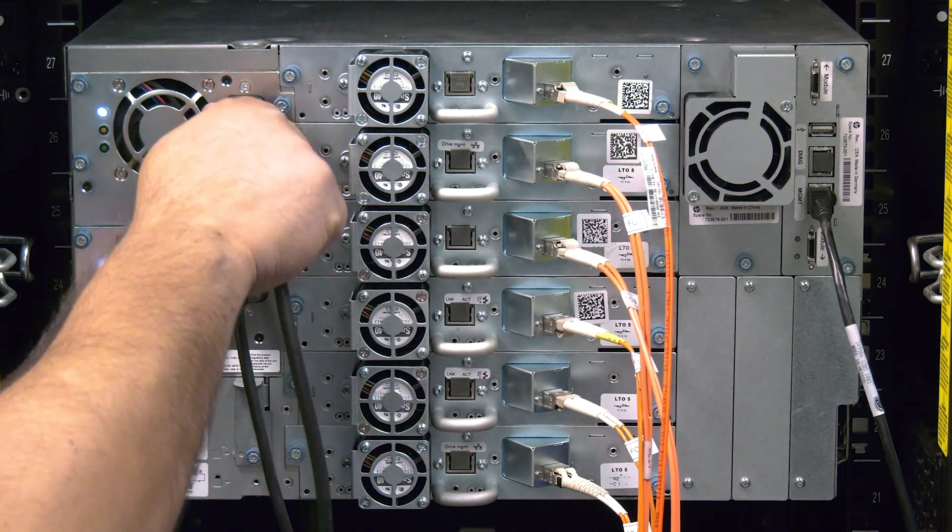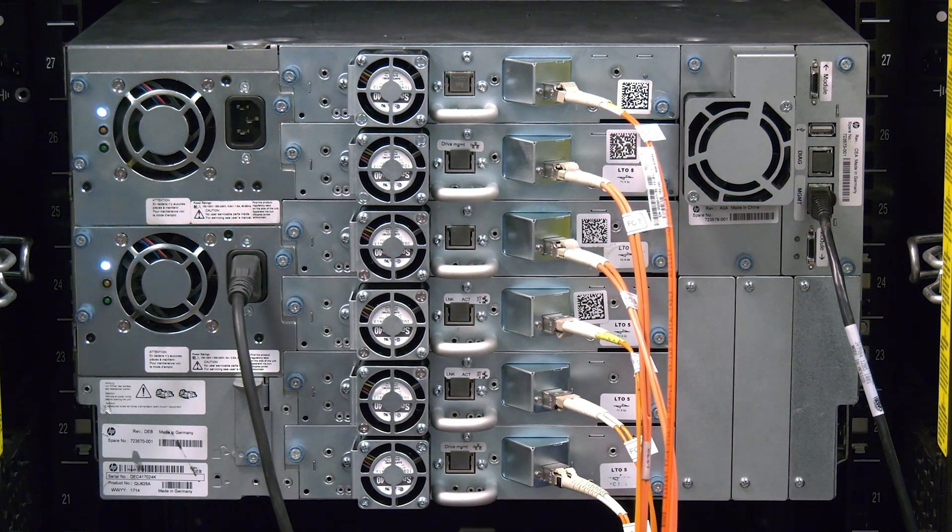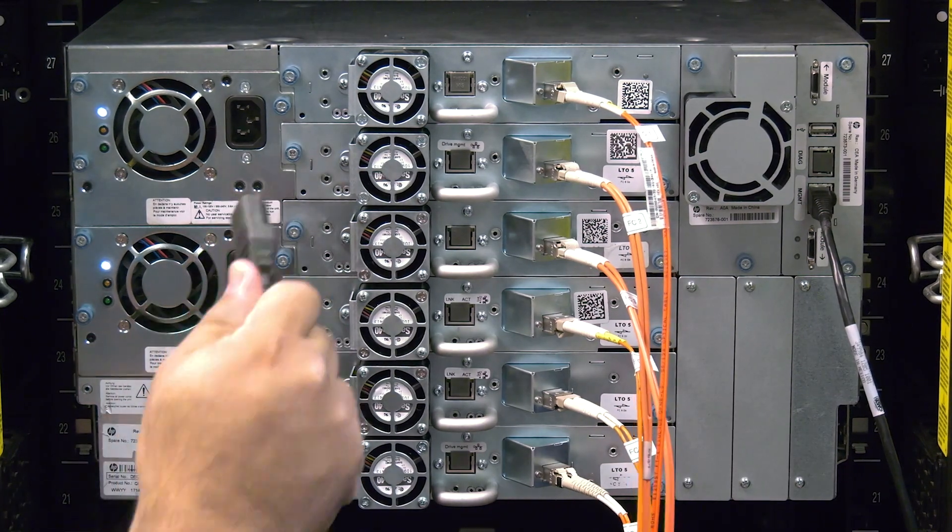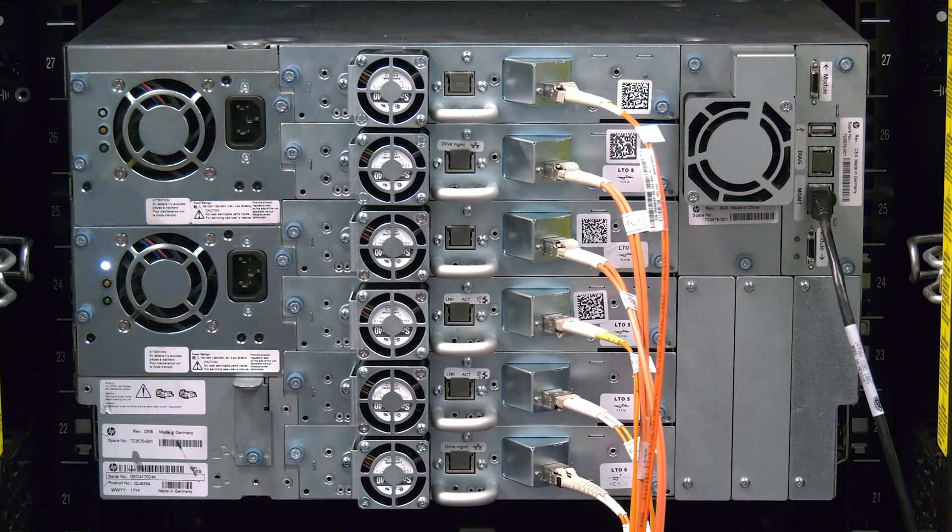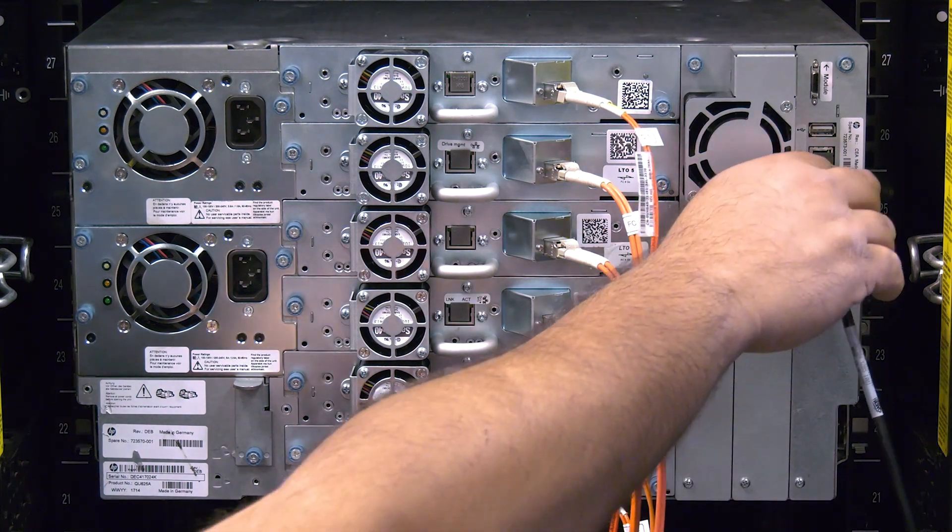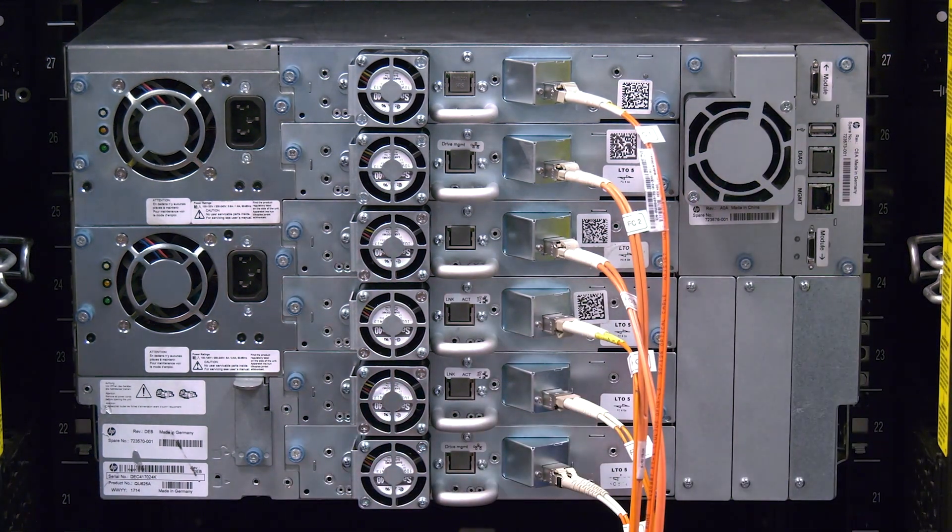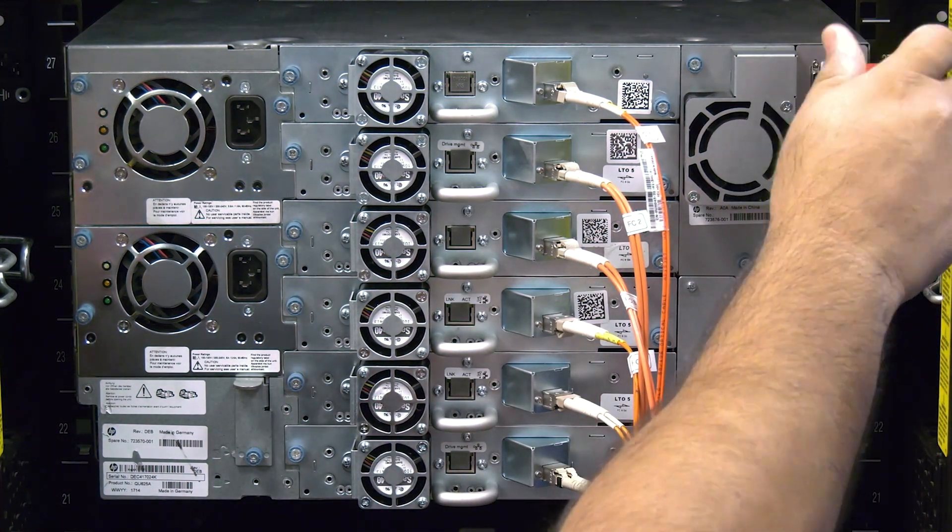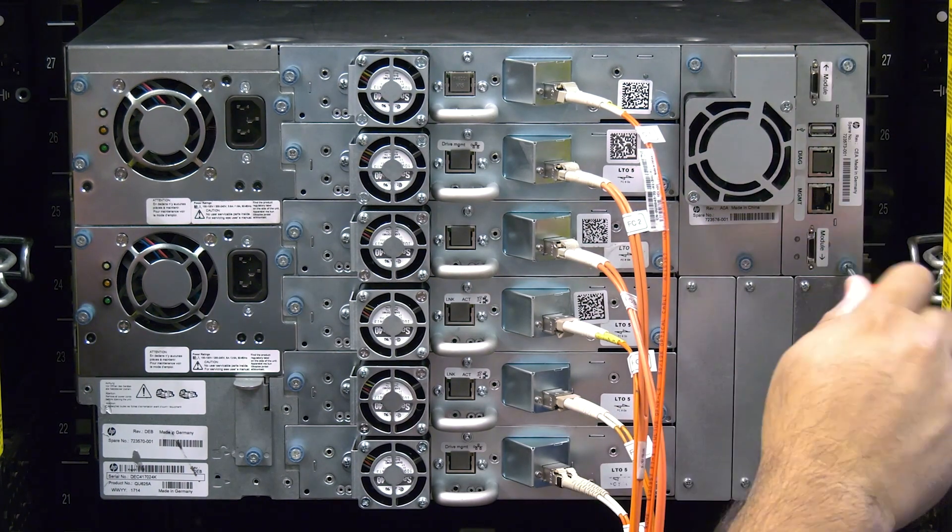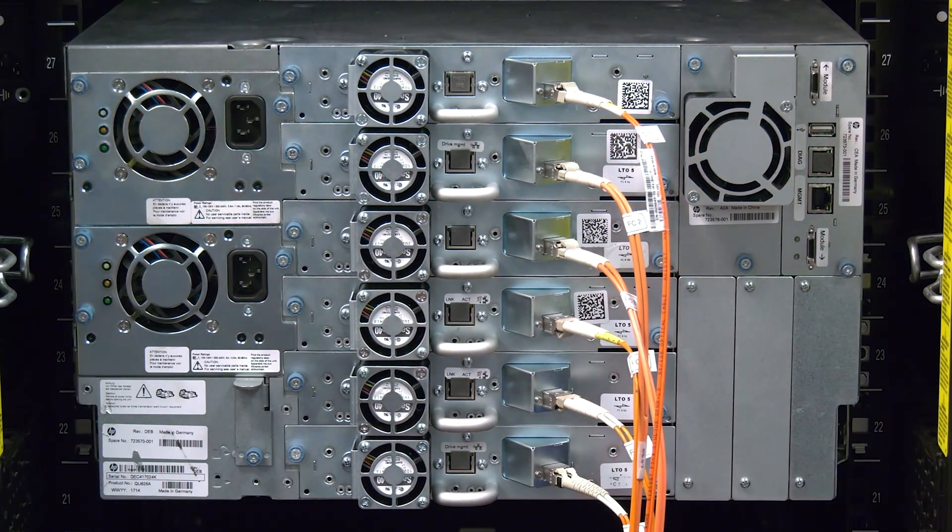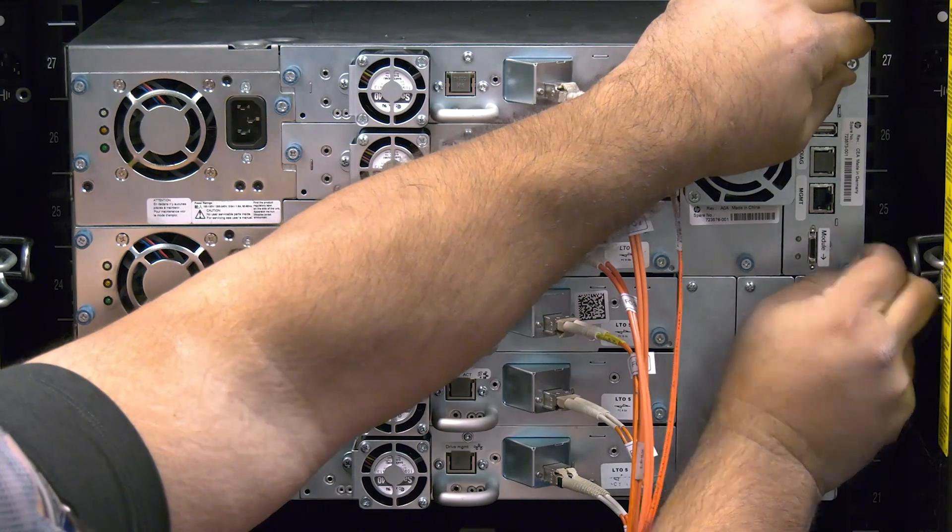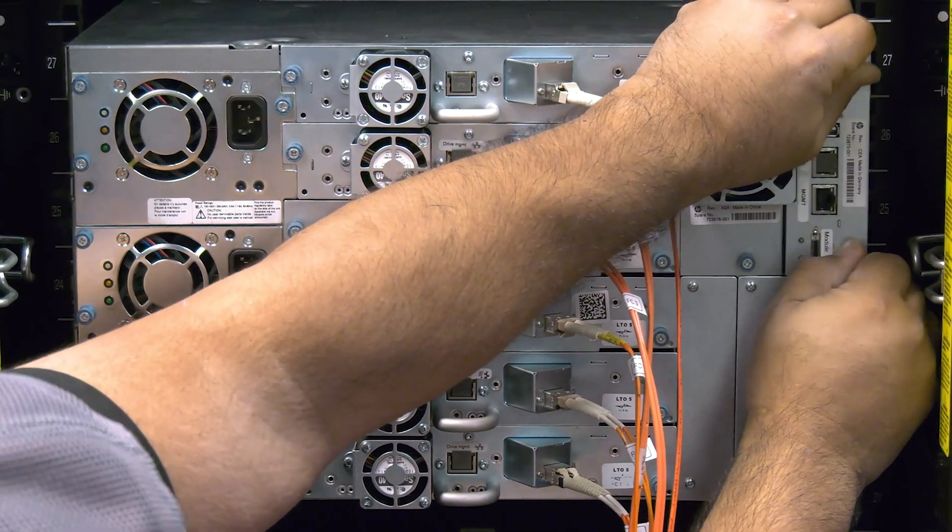First, unplug the power to that module. Then, unplug any module interconnect cables going to the control card if they are present. Also, unplug the ethernet cable from the control card if also present. Then, undo the two blue thumb screws holding the control card into the library. Once they are loosened, you can pull the controller card straight back and out of the library and set it to the side.